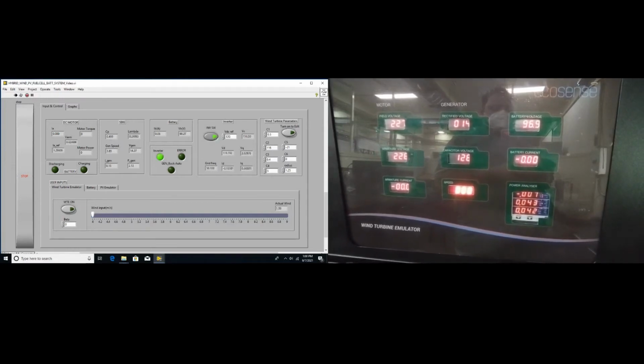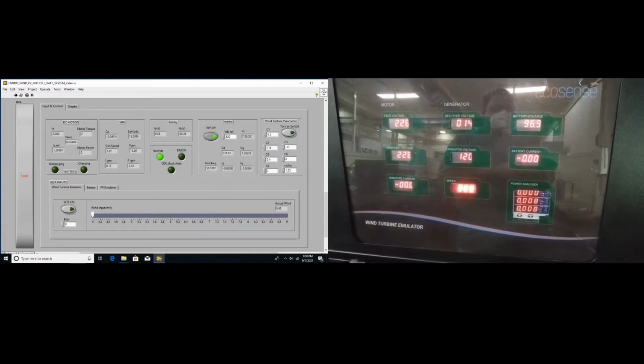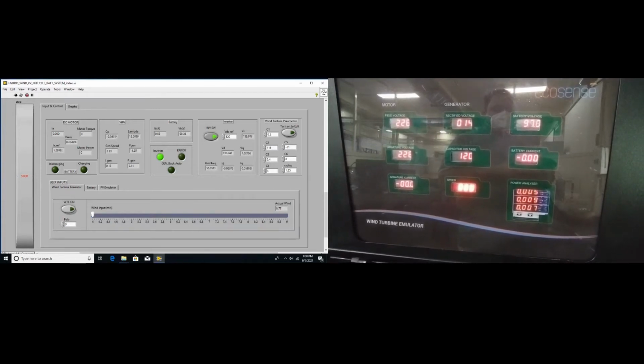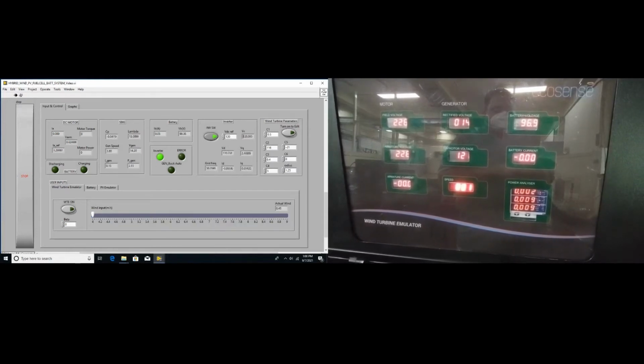As soon as we switch on the inverter, we can see the capacitor voltage climbing up to the reference voltage. And once the DC link is set, let's check the phase sequence. If VD is equal to the peak voltage of the grid measured at the primary side of the transformer and VQ equals 0, then our phase sequence is correct and we are good to go.